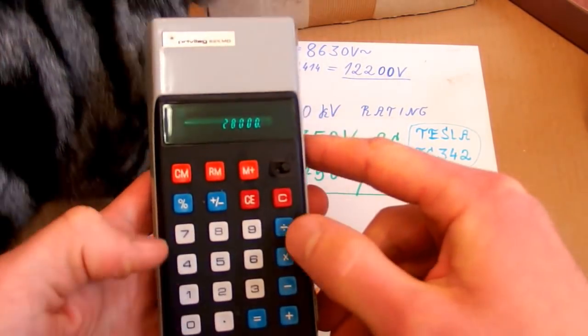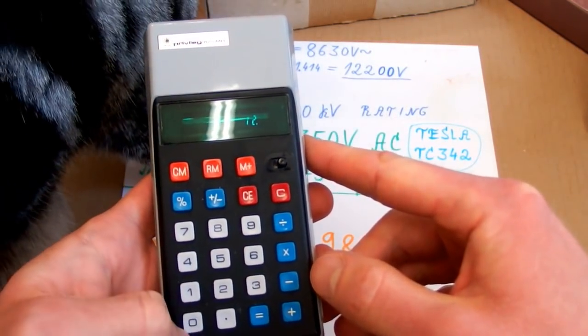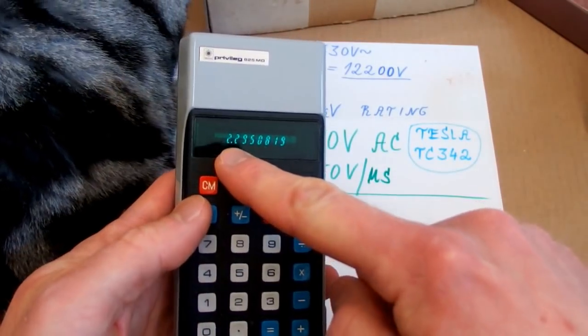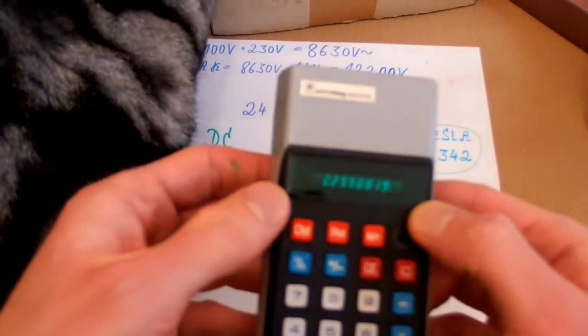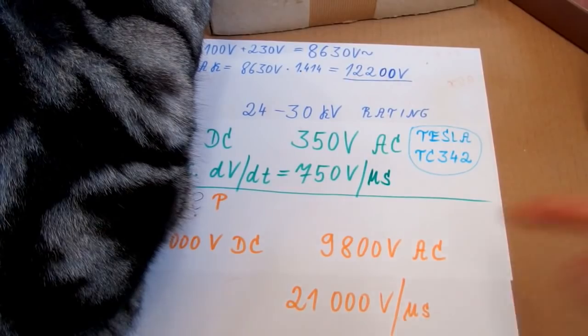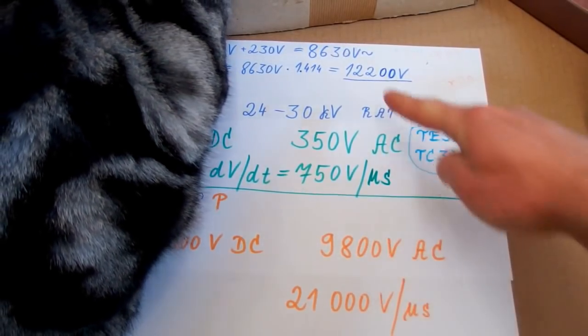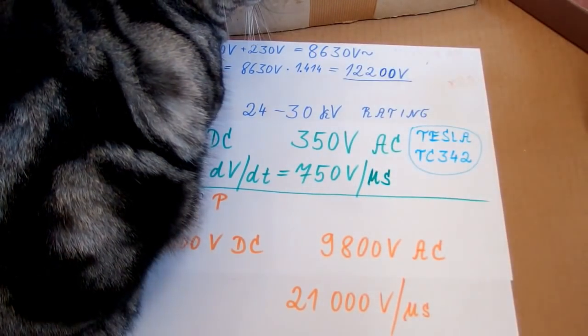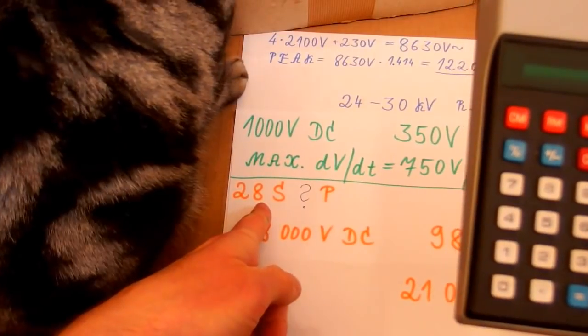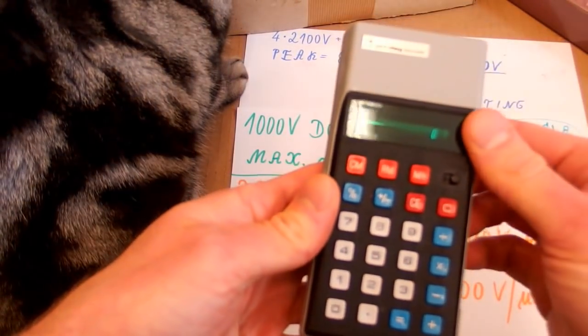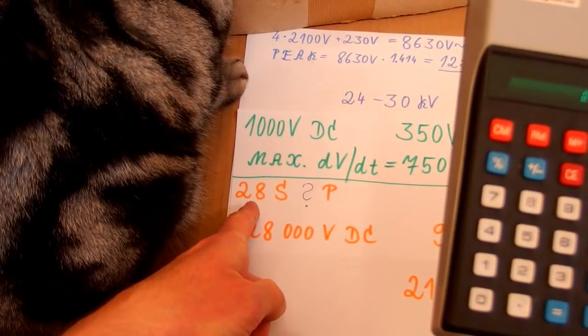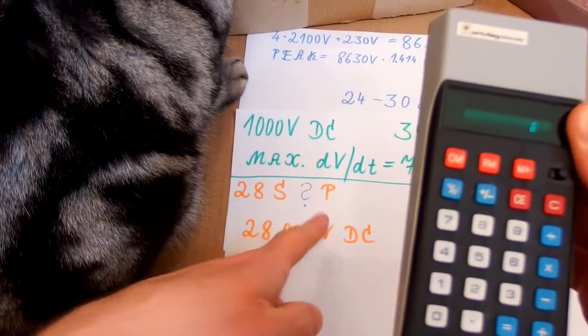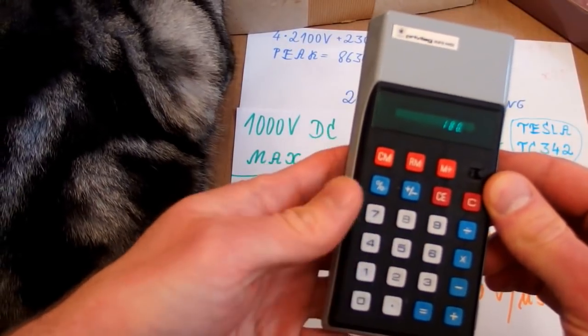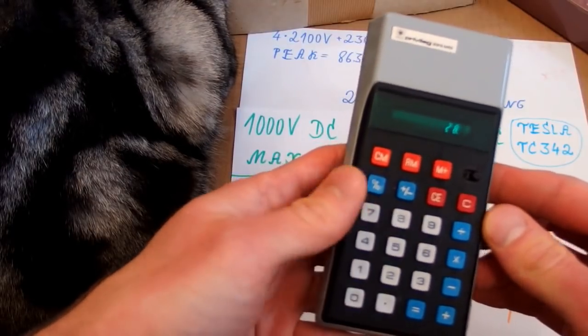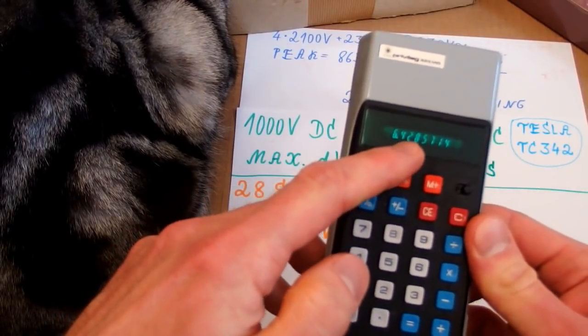And 28,000 volts divided by 12 kilovolts, or 12,200 volts, is... My capacitor bank is rated for 2.3 times the peak voltage of my high voltage transformer. So there is more than double headroom. And the AC voltage rating of my capacitor bank is also higher than the actual AC voltage of my transformer. So I decided on 28 capacitors in series, but I still don't know how many in parallel. So let's calculate the capacitance of the string with 28 series capacitors, but not yet putting them in parallel. So the capacitance 180 nano is going to be divided by 28, and it gives me 6.42 nano.